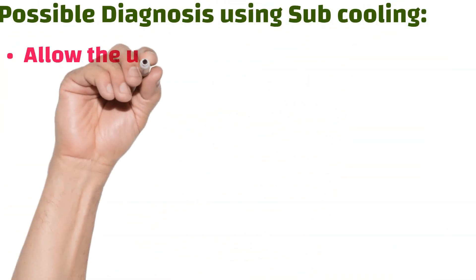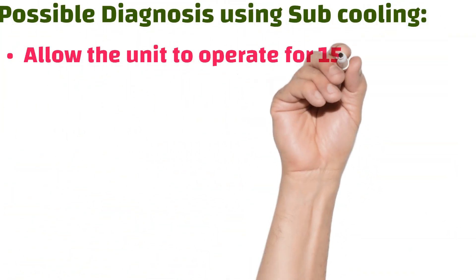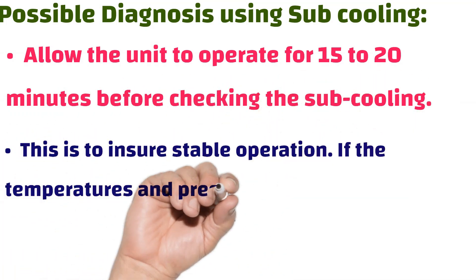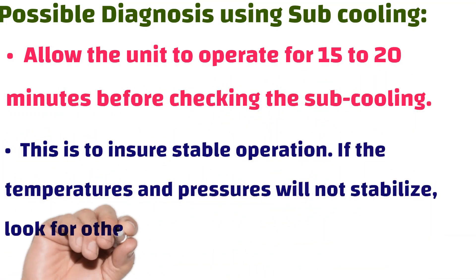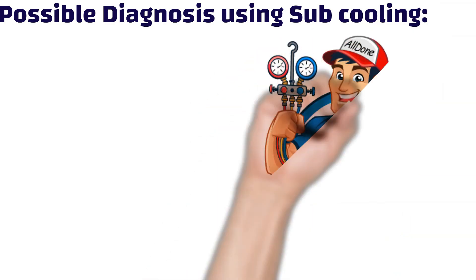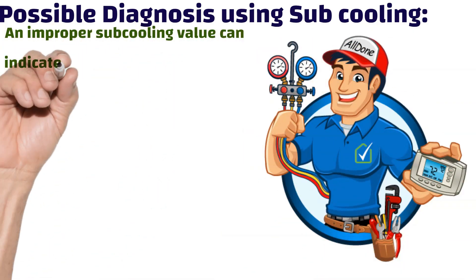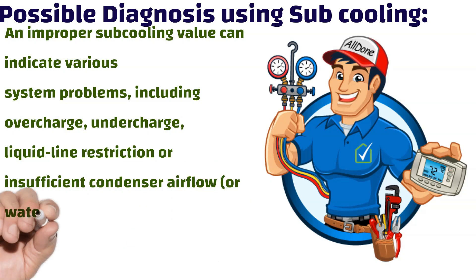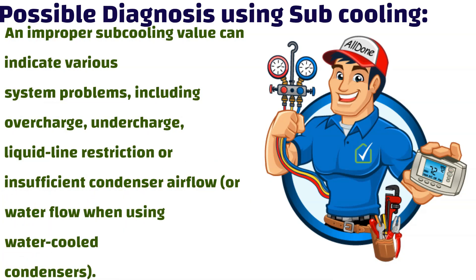For diagnosis using sub-cooling, allow the unit to operate for 15 to 20 minutes before checking sub-cooling to ensure stable operation. If the temperatures and pressures will not stabilize, look for other problems before attempting to check sub-cooling. An improper sub-cooling value can indicate various system problems including overcharge, undercharge, and liquid line restriction.